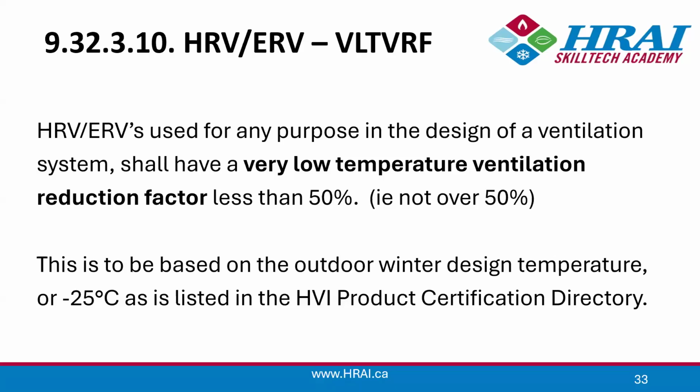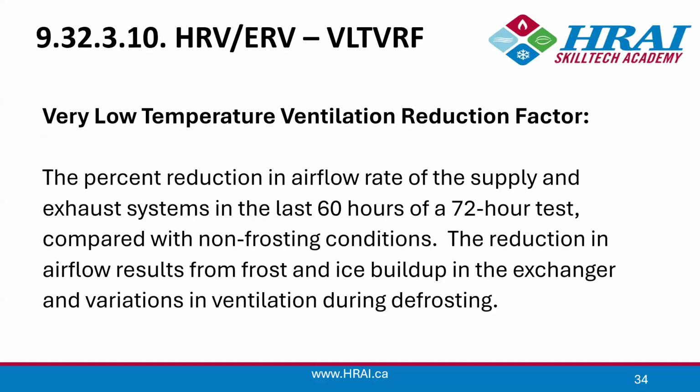So there's a ventilation reduction associated with that. And there's a number assigned to that in terms of the actual laboratory testing that HVI does. So I'll read you their definition of this factor. It's the percent reduction in airflow rate of the supply and exhaust systems in the last 60 hours of the 72-hour test compared with non-frosting conditions. The reduction in airflow results from frost and ice buildup in the exchanger and variations in ventilation rates during defrosting.